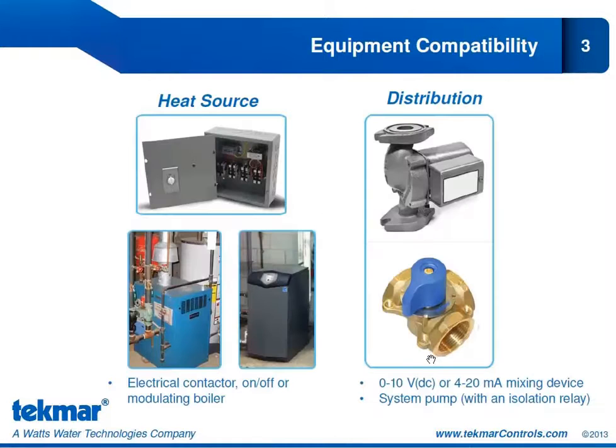So the heat source that the 654 has been designed to accommodate can be an electrical contactor for electrical snowmelt applications. We can also control an on-off boiler or a modulating boiler. As far as the distribution is concerned, we can operate a system pump. Now, when we do operate the system pump, it requires an isolation relay, as you will see when we look at those application diagrams. And for a mixing device, the 654 can operate a 0 to 10 volt DC or 4 to 20 milliamp mixing device. So a little bit different from our previous snowmelt controls. We are now using an analog signal to control the mixing device.